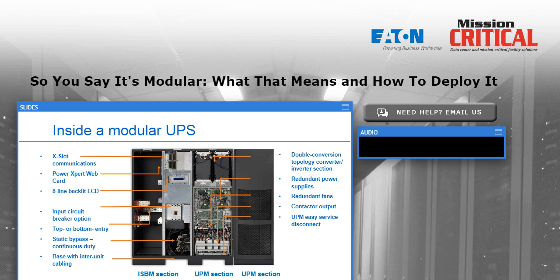And just to the right of that, in the center of the cabinet, you see the input breaker, and in the bottom of that segment, there's a couple of fans you see on the front of a module. That's the static switch with redundant fans on the front, so the loss of a fan doesn't mean an emergency situation for that UPS. That's what we call the system bypass module section, and it's intended by design not to have anything in there that's failure prone. So there are no master controls in this type of system. The controls reside in each of those individual identical UPM modules that we'll talk about on the right. Communication cards for network communications or relay contacts, that type of thing, are in the SBM section, as is the control panel for the UPS.